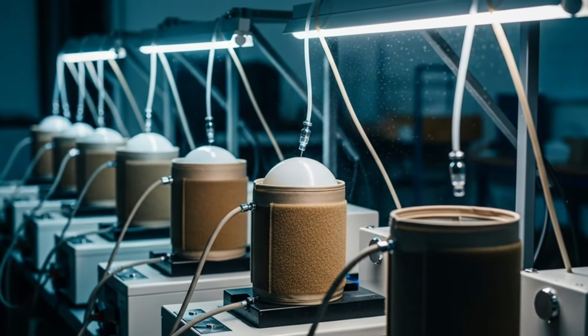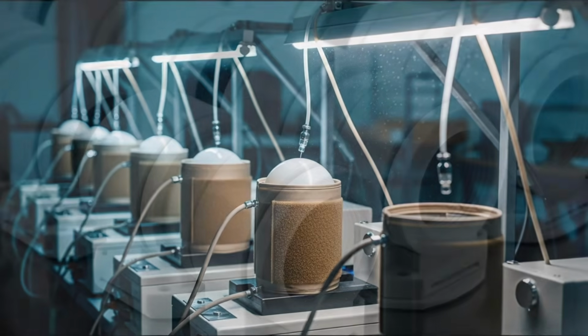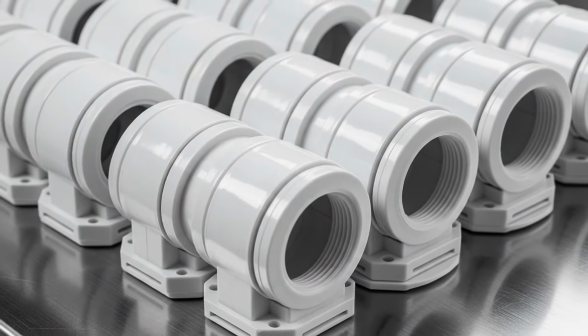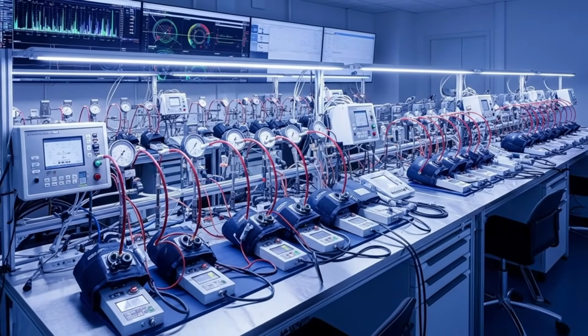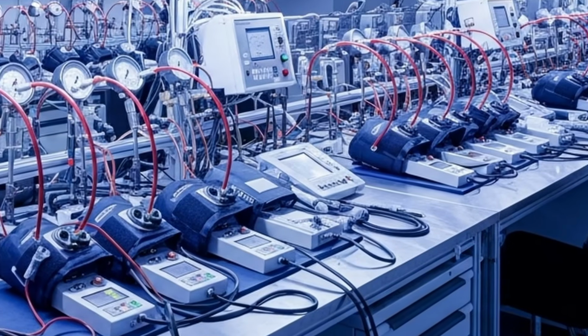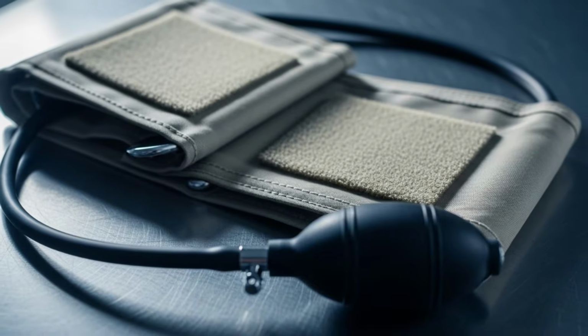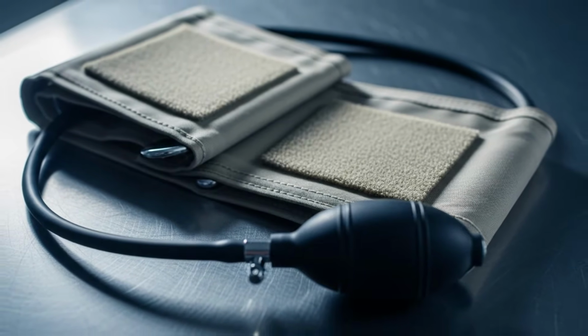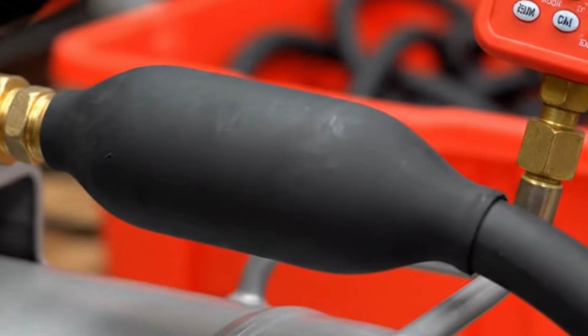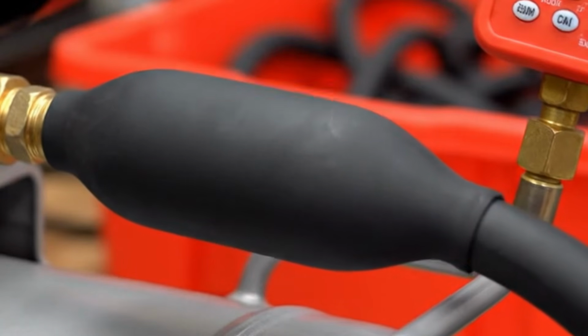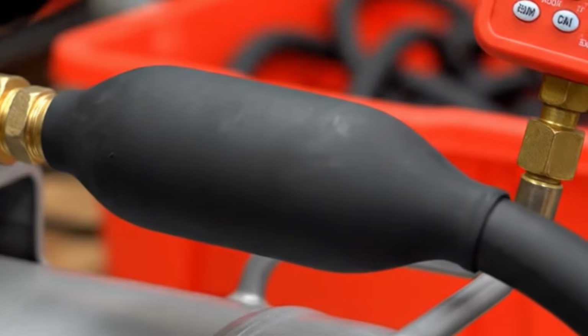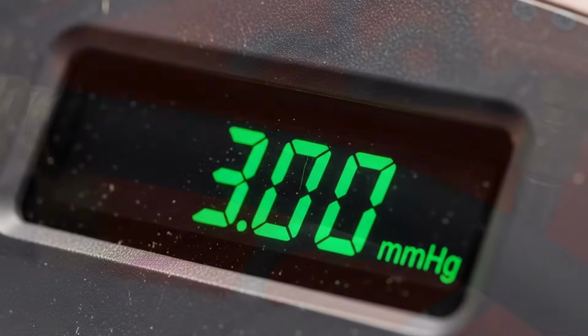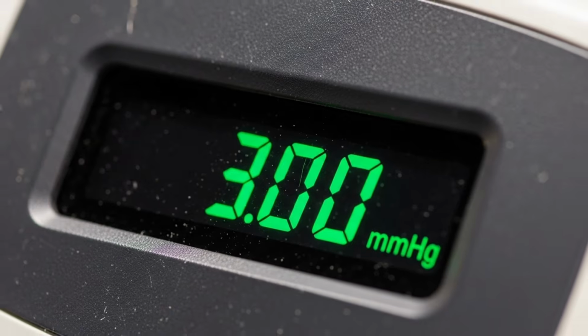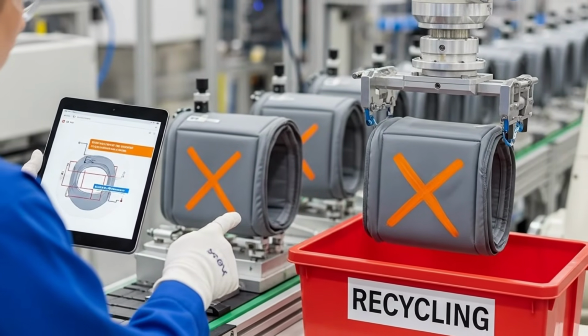Plastic connectors, made through injection molding, are firmly attached to allow connection with the air tubes from the central unit. Then comes testing. Each cuff is inflated repeatedly, simulating real exam conditions. In the control room, multiple units inflate and deflate in unison, like a group of hearts beating together. If one shows leaks, wear, or any defect, it is removed and recycled. In this component, precision is not negotiable. A failure could compromise the entire measurement.